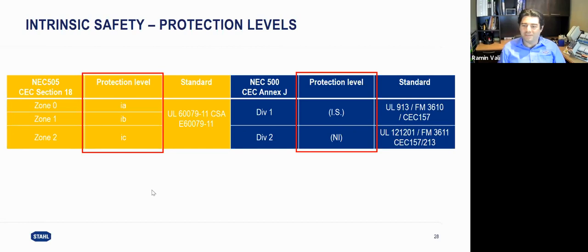And they are all called intrinsically safe, but IA, IB, and IC are the differentiators of the level of the fault. In the NEC 500 or Annex J concept, we just use the IS, intrinsically safe, which is, let's say, 2 levels of fault tolerated, and non-incendive for division 2 installation, which is definitely another discussion.